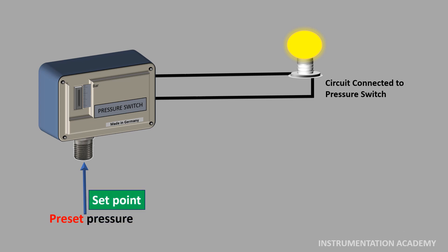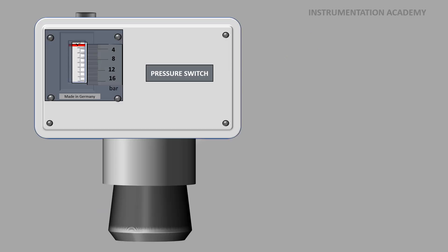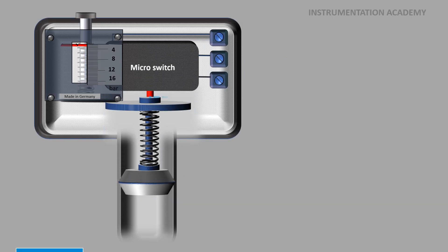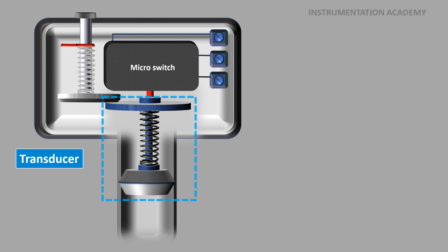Output of the pressure switch is digital, that means output can have only two states: on or off. A pressure switch mainly consists of a transducer which measures the pressure and an electrical switch. The transducer is the part that comes in contact with the process pressure.